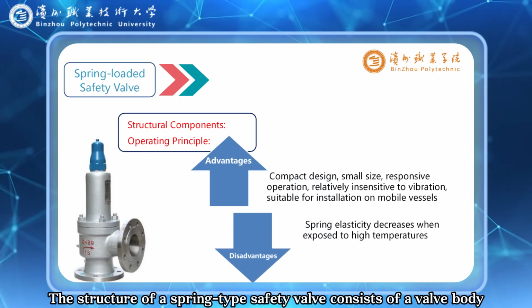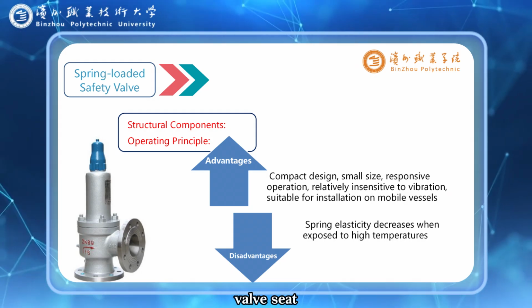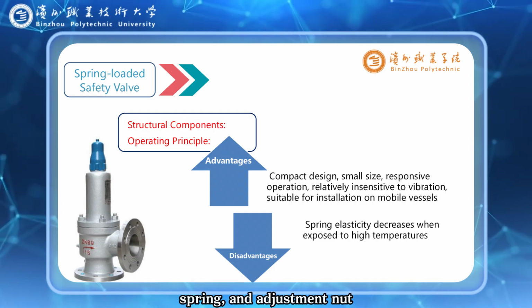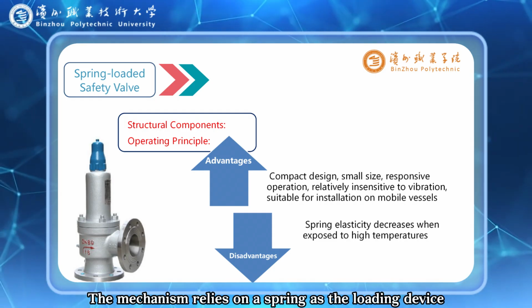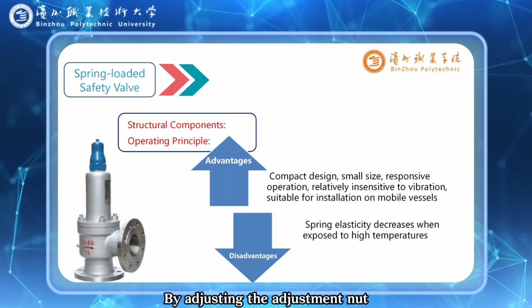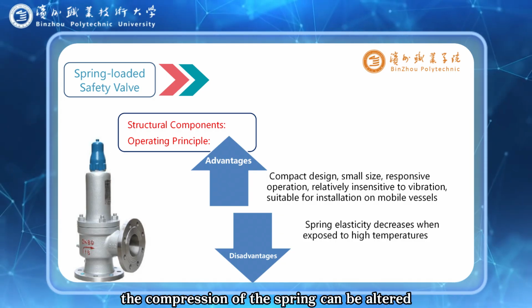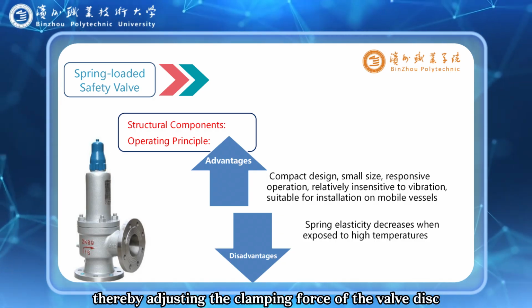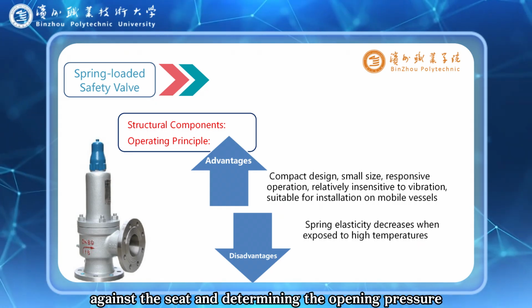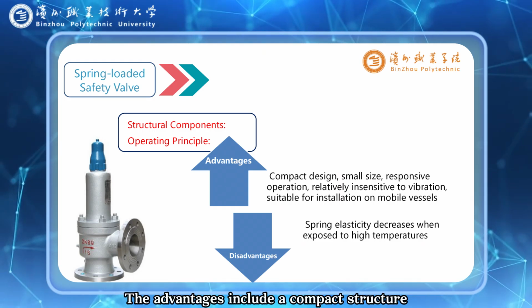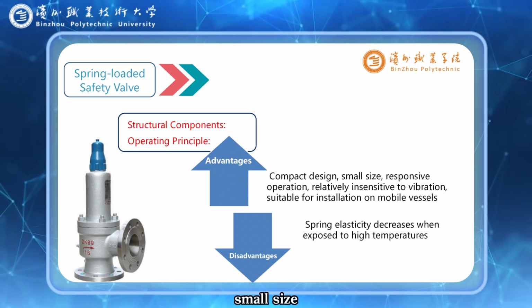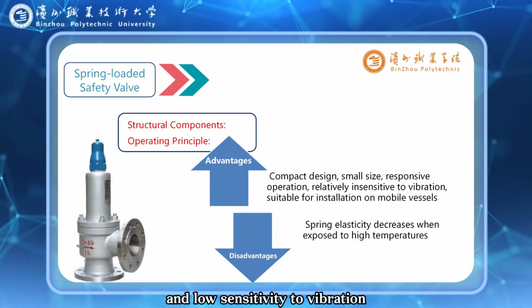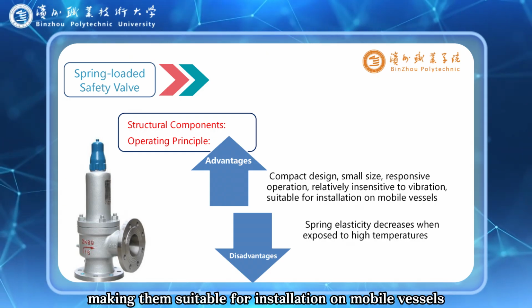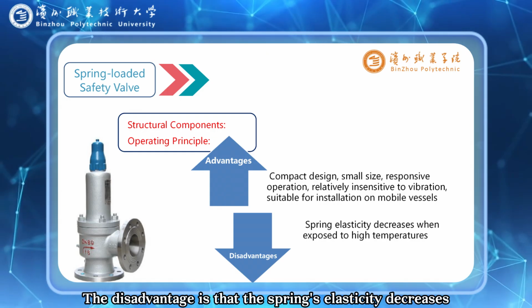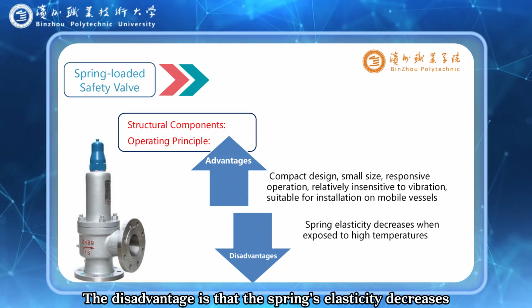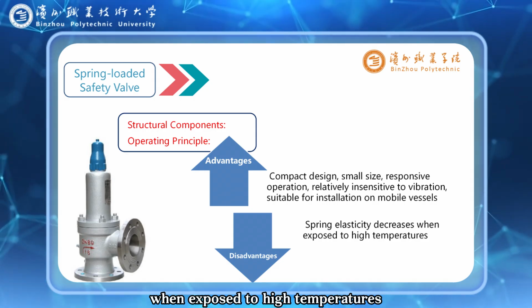The structure of a spring-type safety valve consists of a valve body, valve seat, valve disc, spring, and adjustment nut. The mechanism relies on a spring as the loading device. By adjusting the adjustment nut, the compression of the spring can be altered, thereby adjusting the clamping force of the valve disc against the seat and determining the opening pressure. The advantages include a compact structure, small size, reliable operation, and low sensitivity to vibration, making them suitable for installation on mobile vessels. The disadvantage is that the spring's elasticity decreases when exposed to high temperatures.